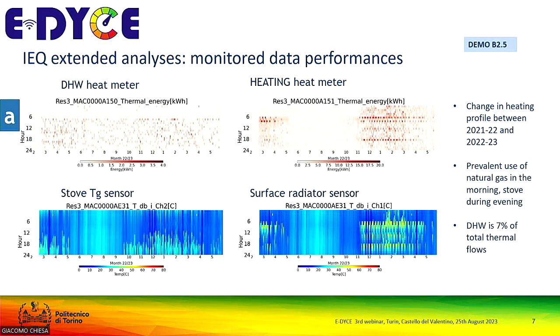From some points of view, it's also possible to see, speaking with the tenants, that we have some variation in the management of the system, and after that they have a sort of reduction in the energy consumption during the project year, 10–15%, something like that. But it's interesting to know that this type of sensor may also allow us to analyze and verify if radiators are correctly used with respect, for example, to the stove, if they need a thermostatic valve to avoid the fact that with the stove the radiator is also pumping in the same room, and so on.